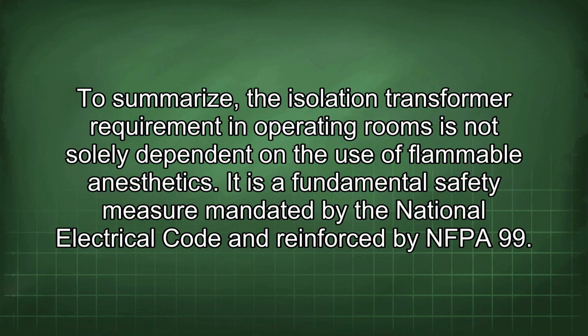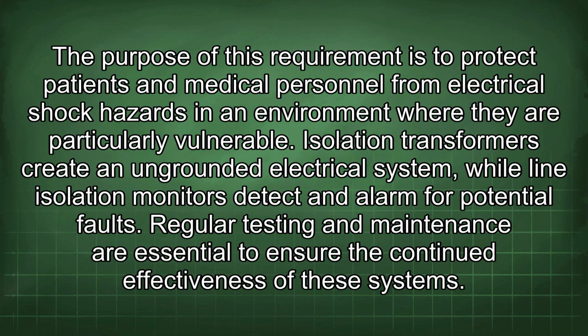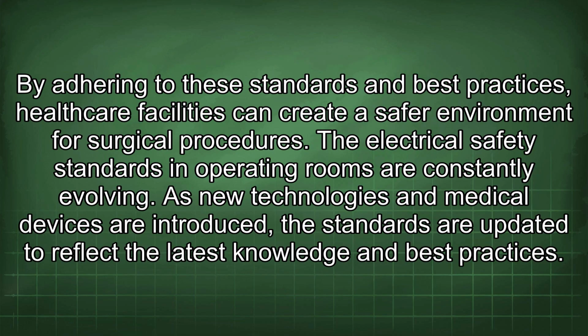To summarize, the isolation transformer requirement in operating rooms is not solely dependent on the use of flammable anesthetics. It is a fundamental safety measure mandated by the National Electrical Code and reinforced by NFPA 99. The purpose of this requirement is to protect patients and medical personnel from electrical shock hazards in an environment where they are particularly vulnerable. Isolation transformers create an ungrounded electrical system, while line isolation monitors detect and alarm for potential faults. Regular testing and maintenance are essential to ensure the continued effectiveness of these systems. By adhering to these standards and best practices, healthcare facilities can create a safer environment for surgical procedures.